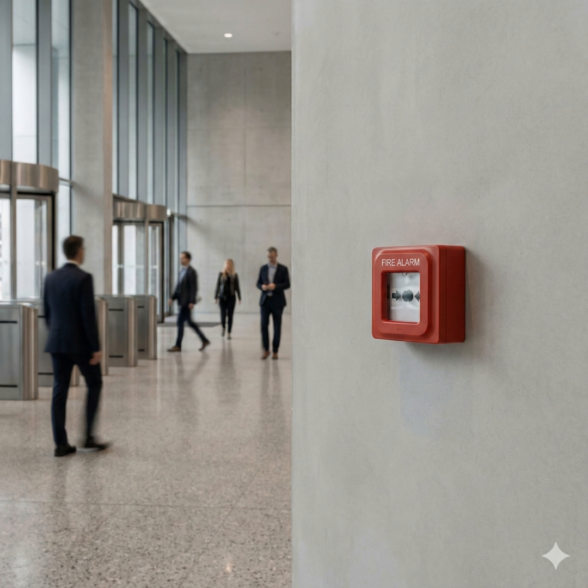Shifting to external signaling, getting the alarm out of the building to the monitoring station. We've moved beyond old telephone circuits, the DACTs. Redundancy in signaling is now mandatory. While DACTs still exist, they're often augmented or replaced by cellular communicators. The gold standard is a dual-path configuration, using both cellular and an IP connection simultaneously. So if one path fails, the other takes over instantly. Correct, and all signaling paths have to be continuously supervised. The monitoring center expects a periodic test signal, a heartbeat. If that heartbeat stops, they know there's a communication failure, even without a fire.